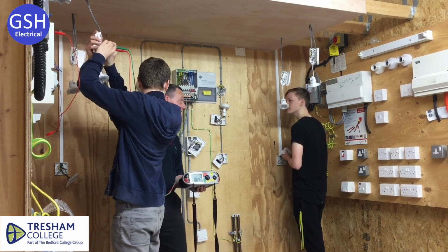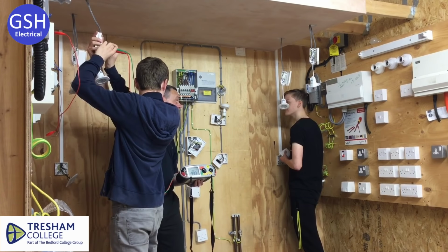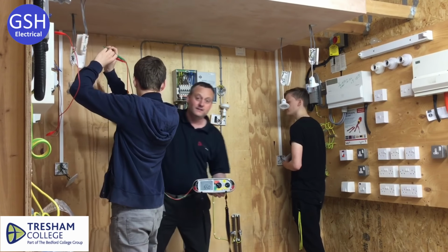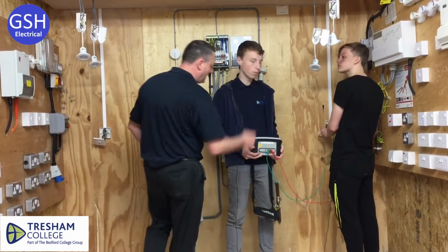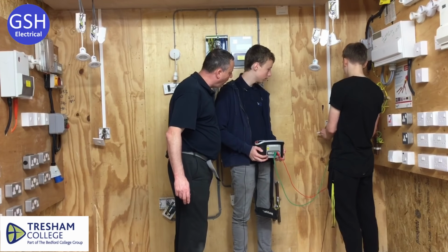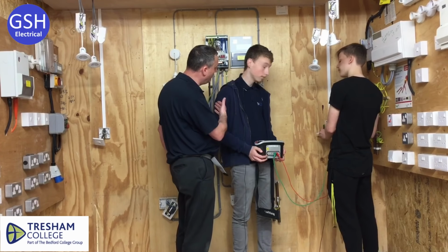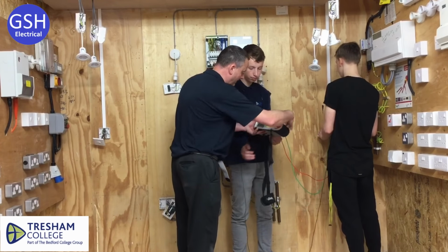Of all the readings to get, Harrison, which one do we record? The highest. Is it complete at this stage, though, having done just the lights? No. Where are we going to test next? The switches. Now we're going to test the switches themselves just to prove there's a CPC down there. Does it need a CPC down there, Harrison? No. Why does it not need one? Because it's plastic. What type of conductive part would a metal light switch be? Exposed.